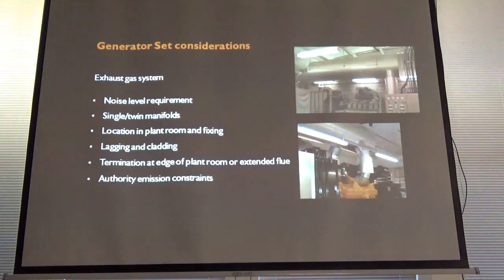Have you had any constraints on flue systems, like for the NOx levels and PM2.5s? Right. What do you see coming in cities? They ask the question more and more, to be honest. There's one site at the moment I'm looking at where they're asking for a selective catalytic reduction system. They've got an overall NOx limit for that site. So it's like, okay, what's the limit? They've told me what the limit is, but also you've got to base it on a certain amount of running hours per year, what you expect. And then, so I asked them to do it in that fashion, so I then work back and say, okay, it relates in turn to the actual performance of the selective catalytic reduction system that I can offer them.